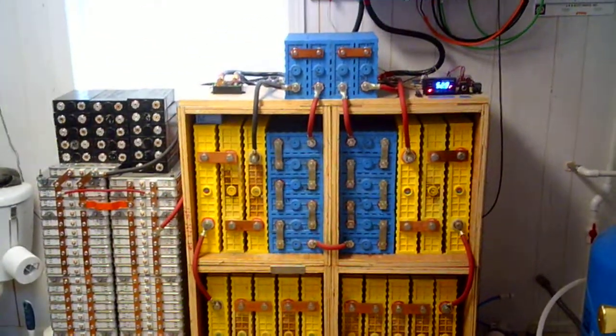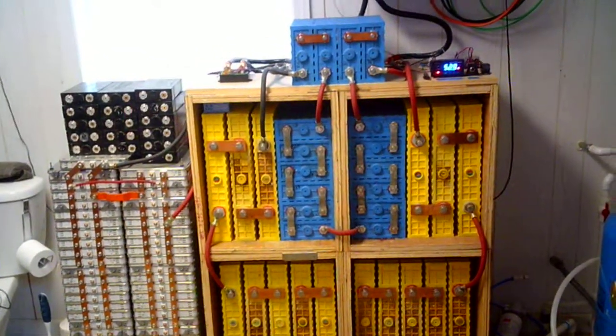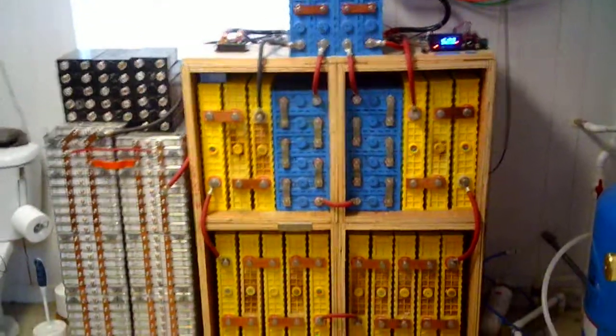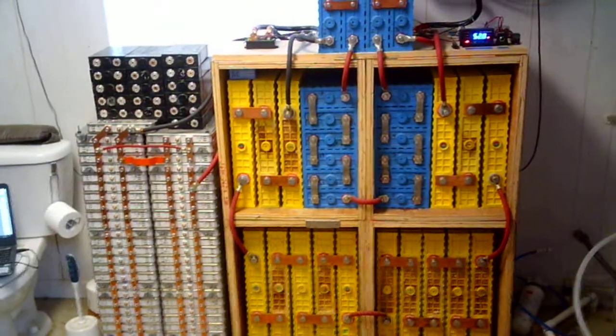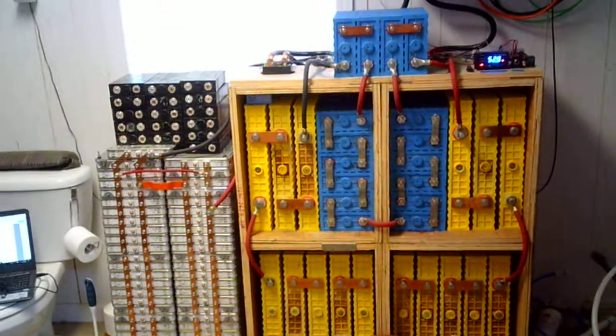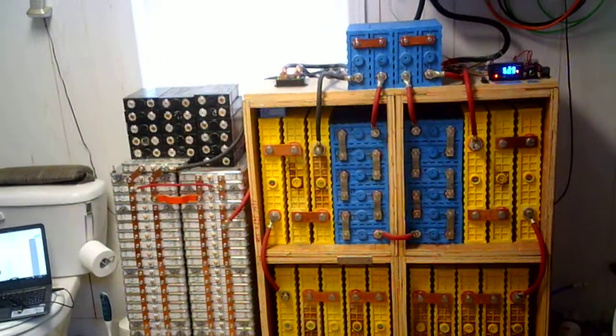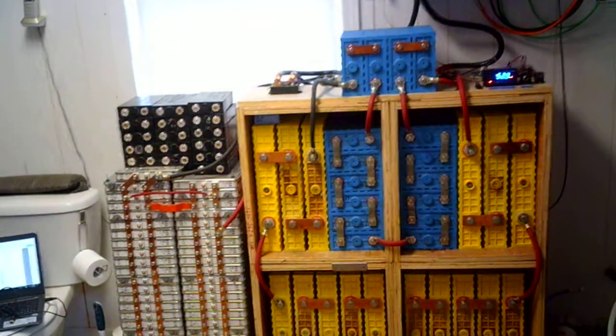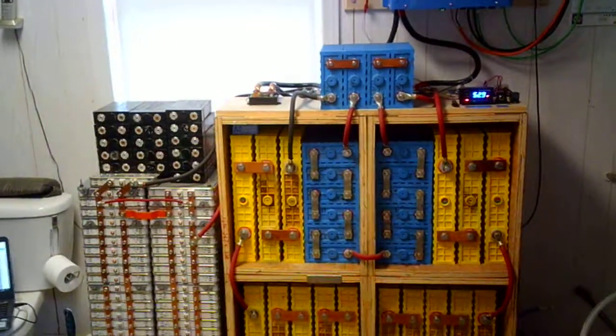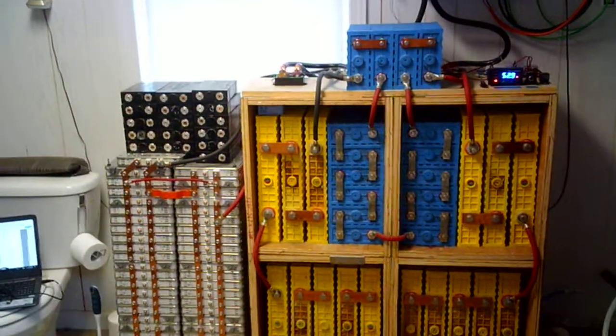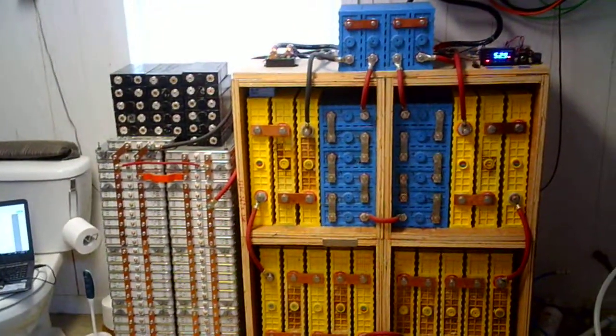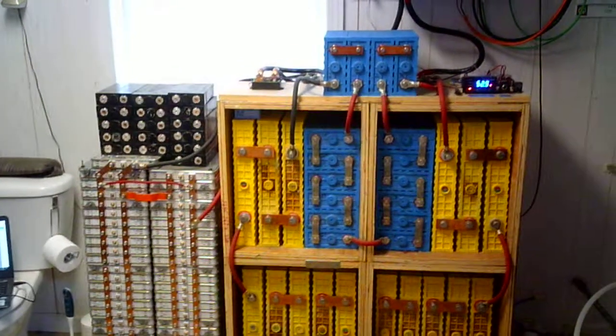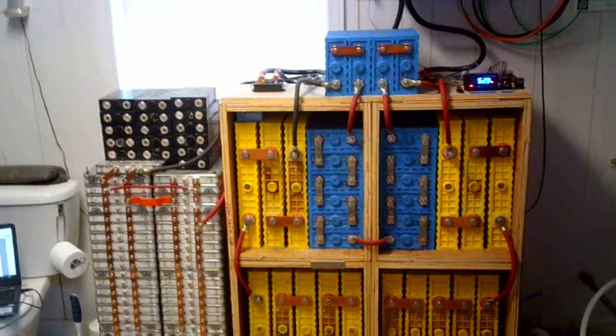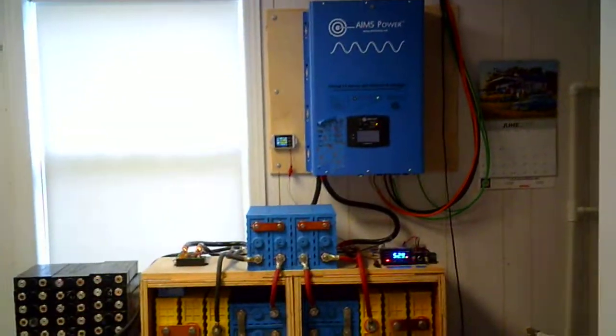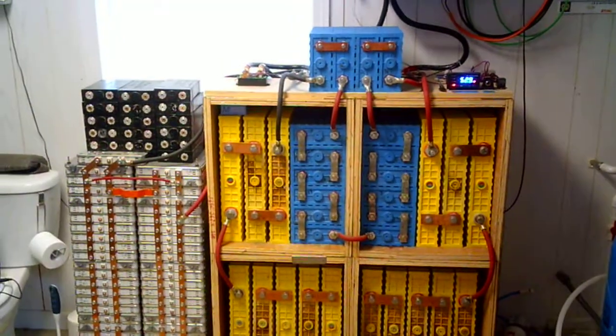The fully charged voltage of this system is 57.6 volts, and the minimum voltage is 40 volts. Under peak sun conditions, when I'm charging at the maximum amount and haven't used the battery, it will charge to 57.6 volts, and at that point a little relay disconnects the charge. I'll get into that a bit more. Under inopportune conditions, no sunlight and batteries are dead, the inverter will shut the system down when it hits 40 volts.